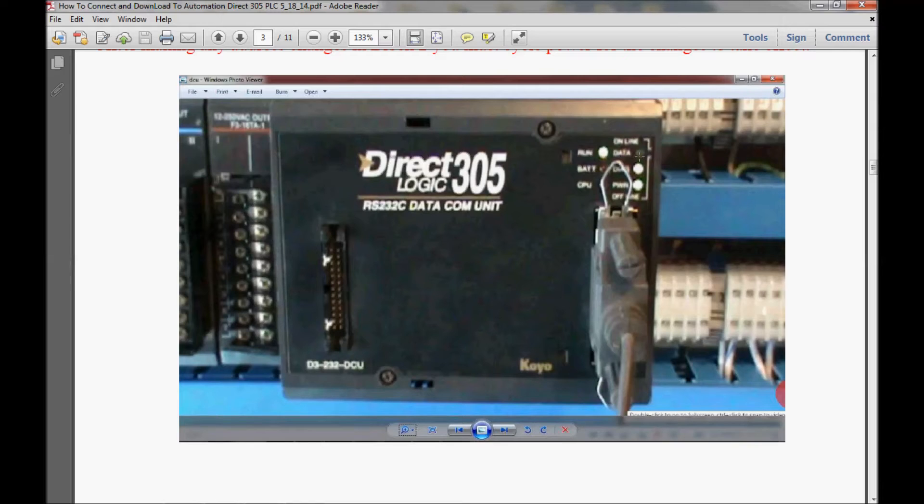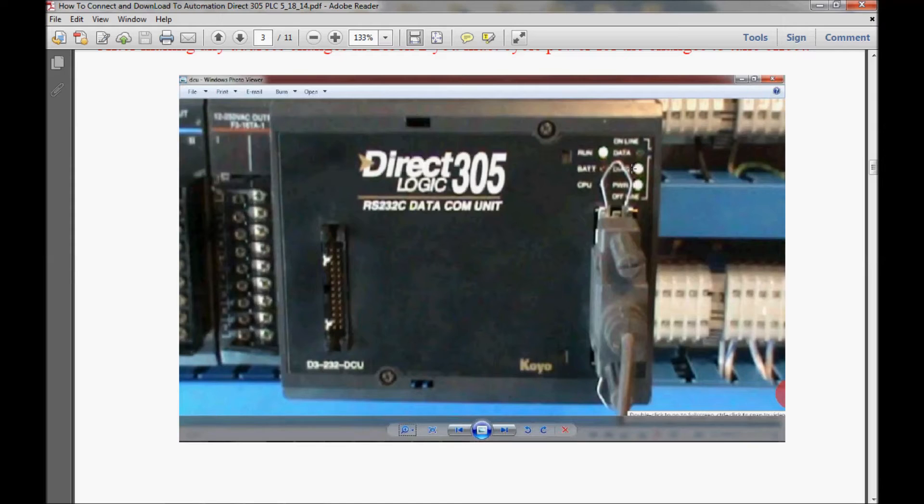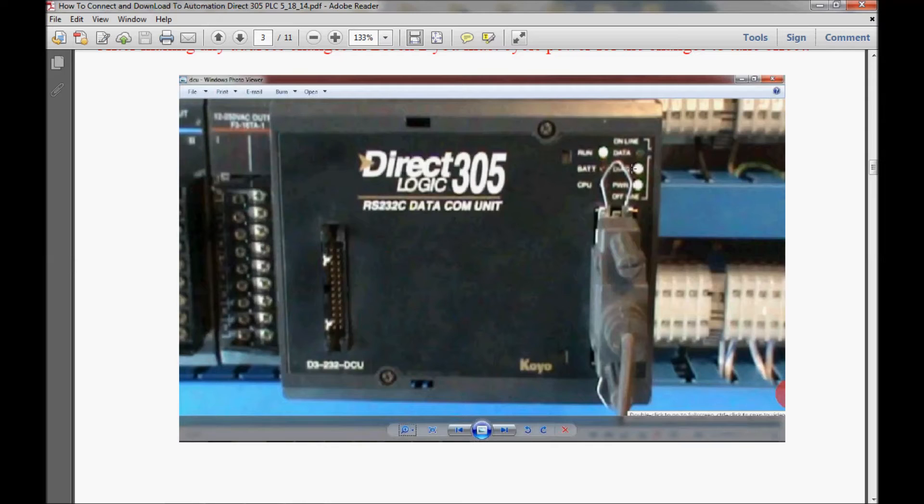Just below that is a diagnostics LED. When the unit is first powered up, whether it's a power cycle of the PLC or if you're just plugging it in, it will perform a self-diagnostics on the unit. If it passes, the green LED will turn on. If it does not pass, it will not be on. If it does not pass, what you can try is a lot of times the base on the PLC, the power supply, starts to weaken. If you're using the internal power supply, you can try powering everything down, making sure that your switch on the back is selected properly, reinstall it, and pull out a few of your input and output cards to reduce the power budget on that power supply. Maybe that will allow the diagnostics to come up and illuminate that LED.